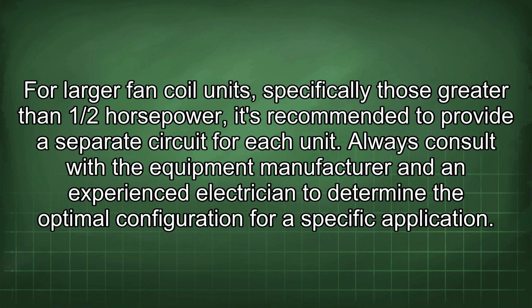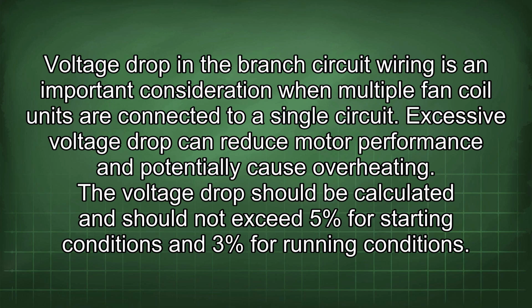For larger fan coil units, specifically those greater than 1/2 horsepower, it's recommended to provide a separate circuit for each unit. Always consult with the equipment manufacturer and an experienced electrician to determine the optimal configuration for a specific application. Voltage drop in the branch circuit wiring is an important consideration when multiple fan coil units are connected to a single circuit. Excessive voltage drop can reduce motor performance and potentially cause overheating. The voltage drop should be calculated and should not exceed 5% for starting conditions and 3% for running conditions.